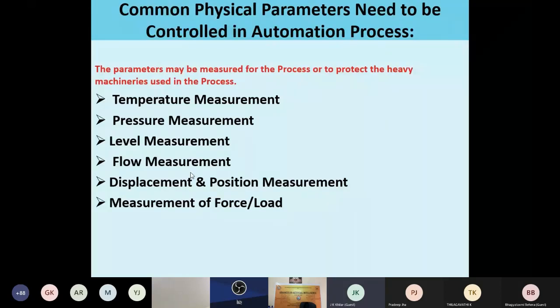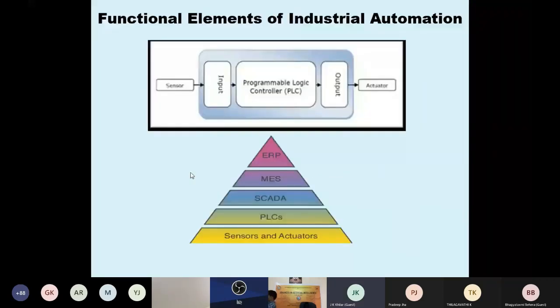And also, to protect a motor or any costly devices, we are providing temperature measuring and also vibration measuring. Like this, different parameters are required to be measured inside the process plant. The functional element of industrial automation: the sensor signal goes to the programmable logic controller, and then the PLC, according to the program, will generate output. Then the output will go to the actuator. So the sensor is the input transducer and the actuator is the output transducer.